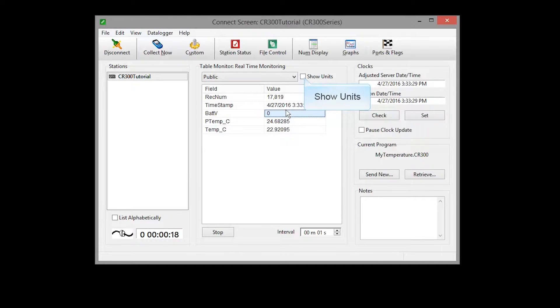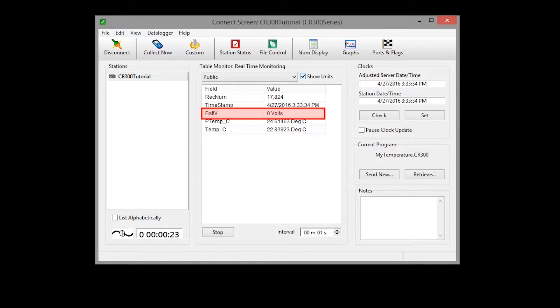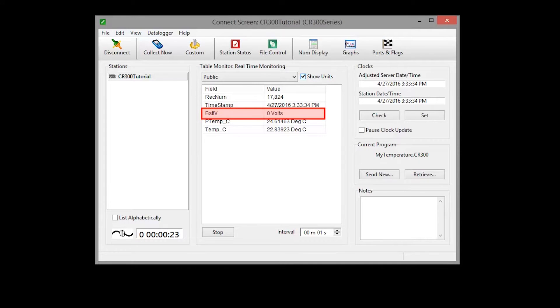Selecting the show units checkbox displays any units that have been assigned to the data values in the table. Note that the battery voltage reads zero when our CR300 is powered by USB. That's to remind you that you need a 12 volt battery for field deployment.